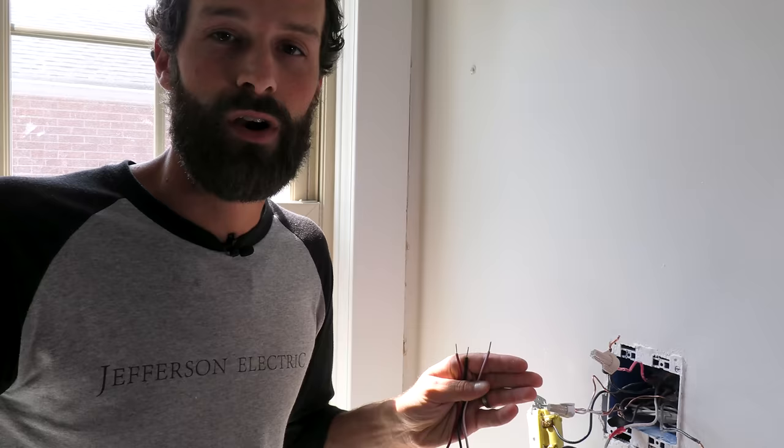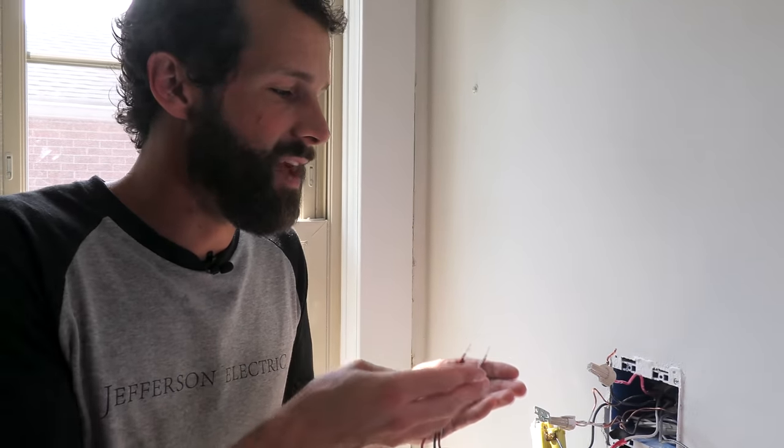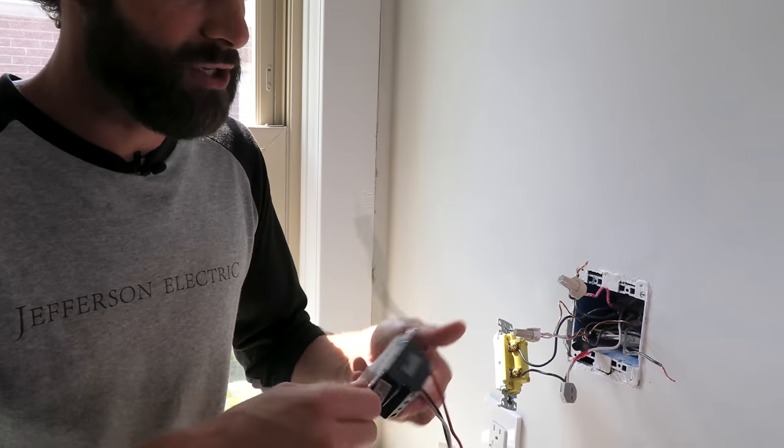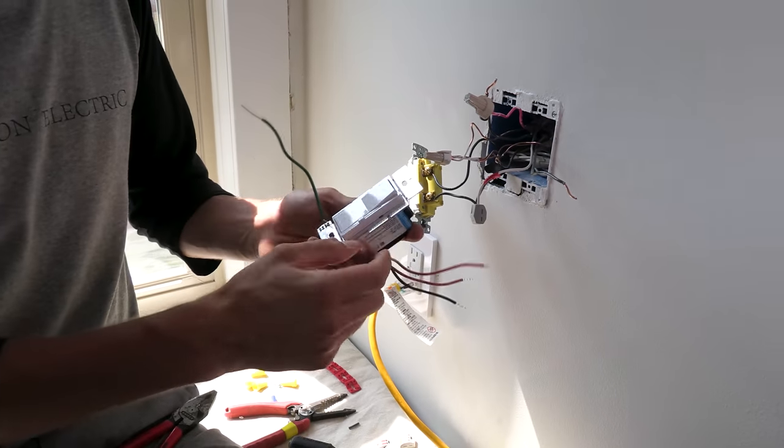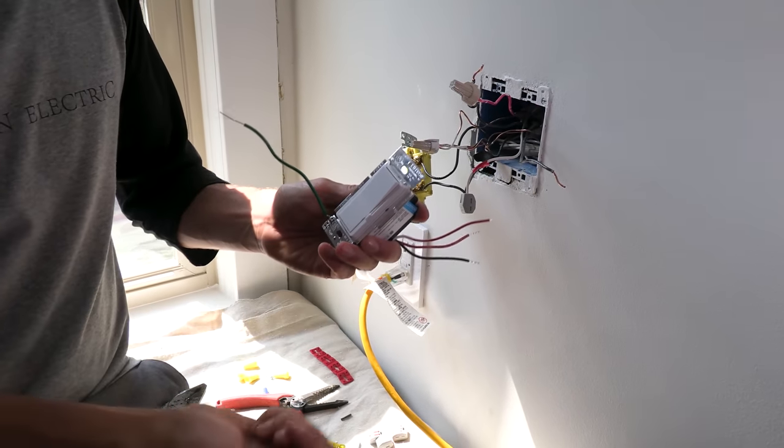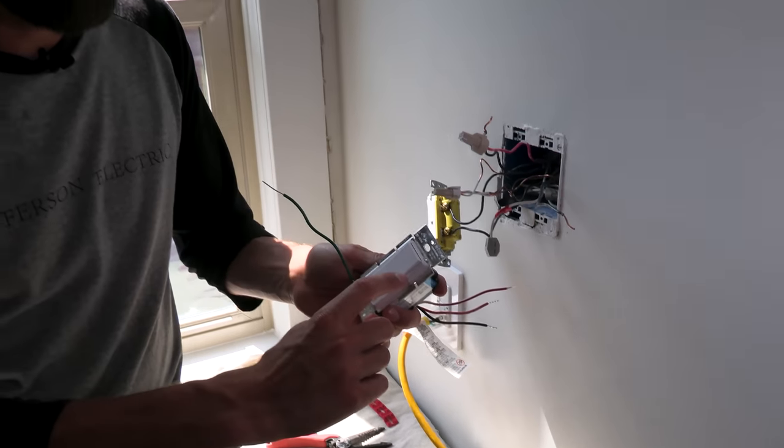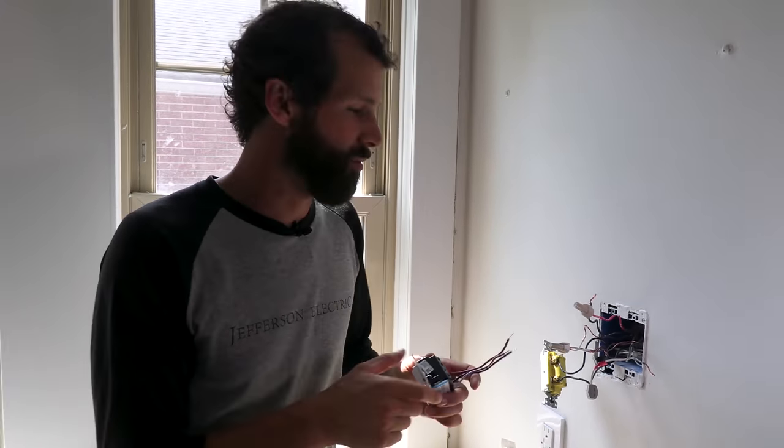you can only have one dimmer on a three-way lighting circuit. And the reason for that is if you've got dimmers at both locations, you'll be constrained to the lowest common denominator. If one's dimmed down all the way, and you go to the other dimmer, and you try to dim it up, nothing's going to happen. You're constrained by the lowest common denominator. So, one dimmer on a three-way or a four-way.